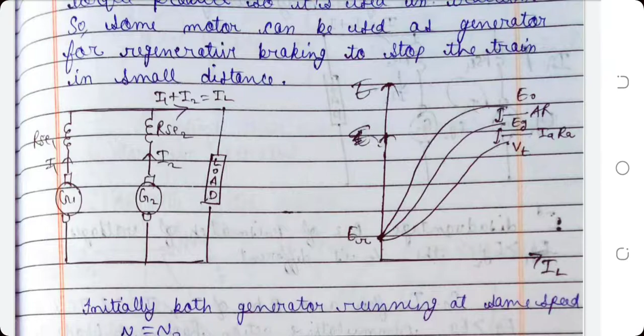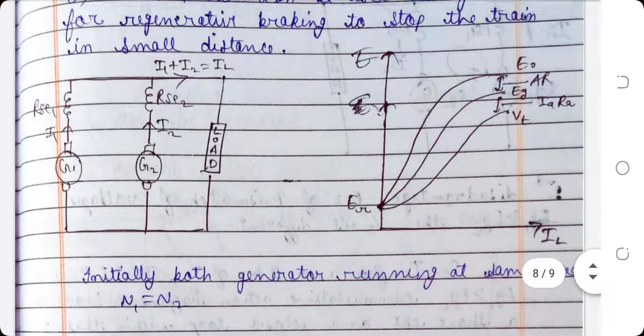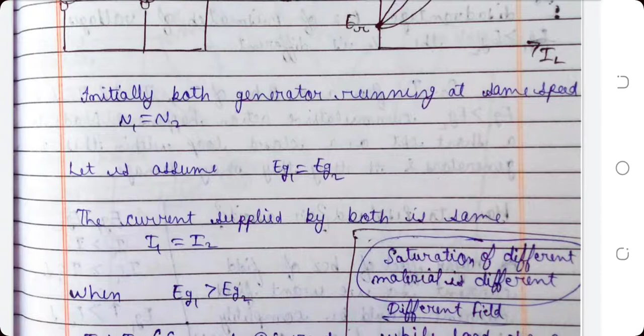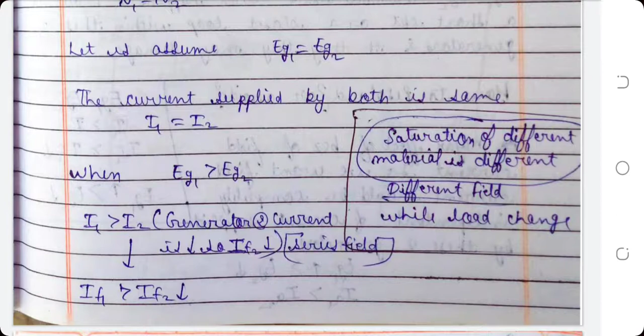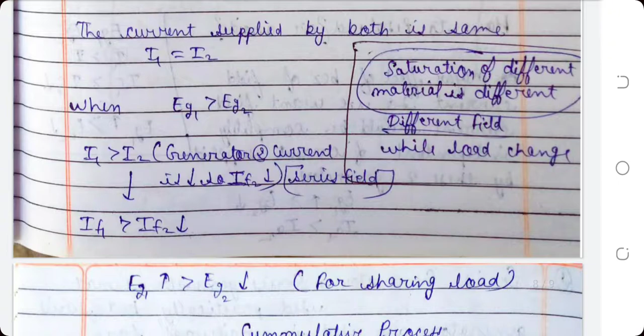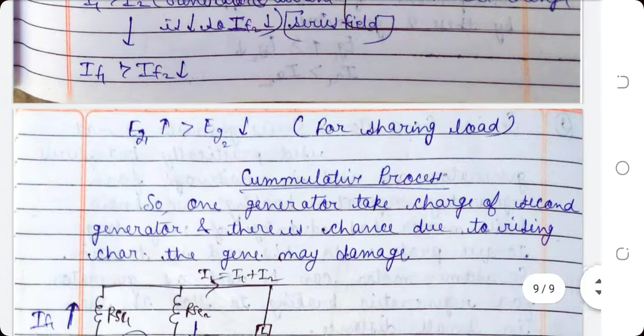So we can see that initially both generators are running at the same speed, so N1 equals N2. Let us assume Eg1 equals Eg2. So the current supplied by both is the same, I1 equals I2. When Eg1 is greater than Eg2, I1 is greater than I2. Generator 2 current decreases, so IF2 also decreases. This is for the series field. Saturation differs in different fields while the load changes. That's why IF1 is greater than IF2, and that is why Eg1 is greater than Eg2 for sharing load.